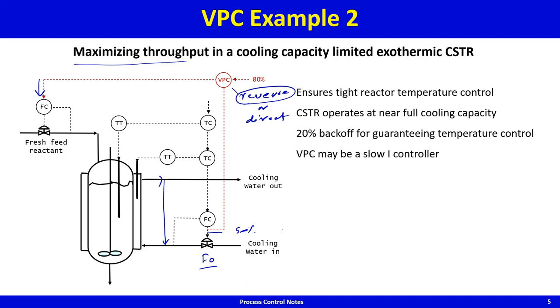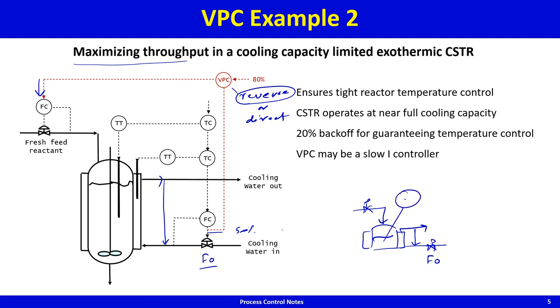This valve positioning control scheme ensures tight reactor temperature control, because reactor temperature control is always through the cooling circuit. One might consider instead keeping the cooling valve fully open and controlling reactor temperature by adjusting the fresh feed, but the problem with this alternative is the possibility of reaction runaway.